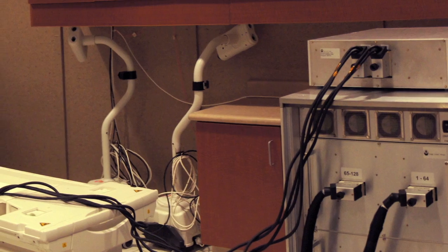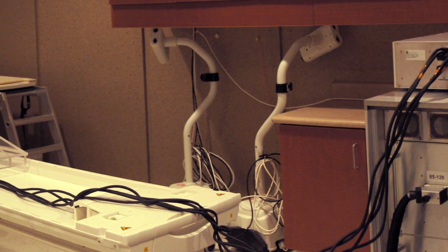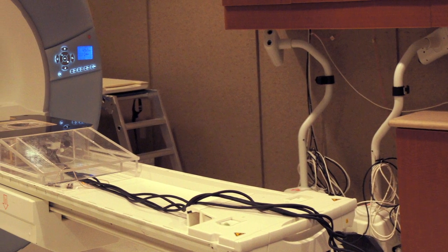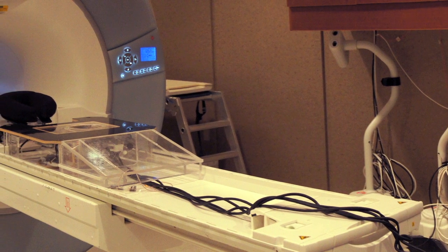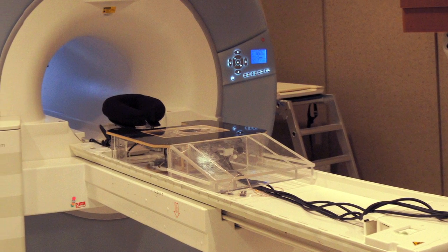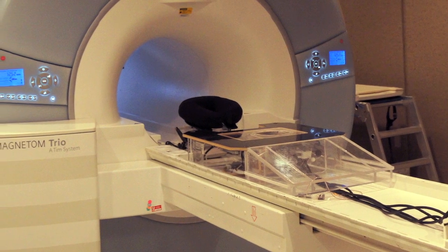The rest of the system is an MR-compatible ultrasound generator made by our collaborators at Image-Guided Therapy in Bordeaux, France. And of course Siemens is the MRI scanner. They've been very helpful with the radiofrequency system and also with temperature imaging pulse sequences. We've developed primarily our own sequences that we're using, but it is this three-way collaboration. We've tested it on phantoms and other samples.